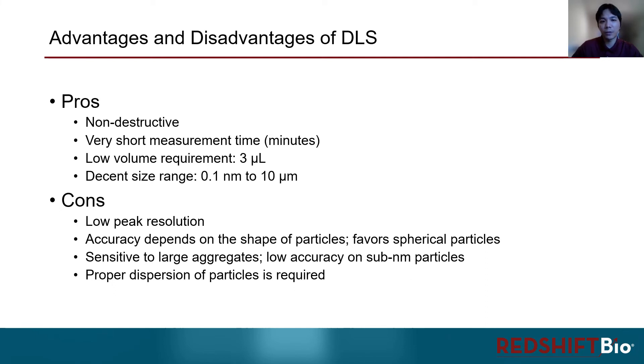Some of the disadvantages include low resolution. Particles that are only a few nanometers apart usually cannot be distinguished by DLS. DLS treats all particles to be spherical in shape. So if the particles are not spherical, the accuracy might not be guaranteed. Also, DLS is more sensitive to larger particles, such as aggregates or dust, and less accurate for smaller particles. And finally, particles need to be in homogeneous dispersion for the measurement.